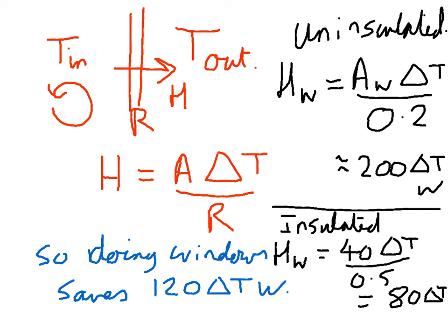In principle, you could put in your energy price and a typical temperature difference. So let's say in winter it might be on average 5 degrees outside, and let's say your thermostat to 20 degrees inside. Delta T is 15. That will tell you how many watts are coming out, so you can actually work out how much it's going to cost.